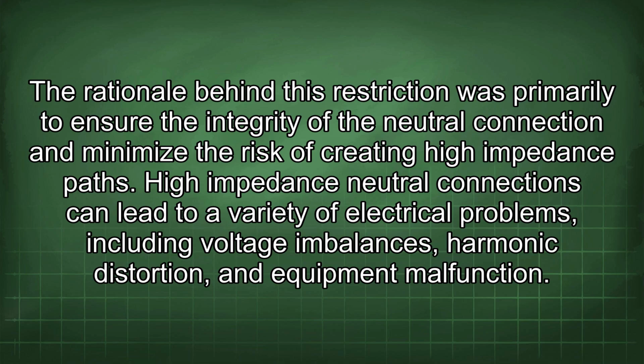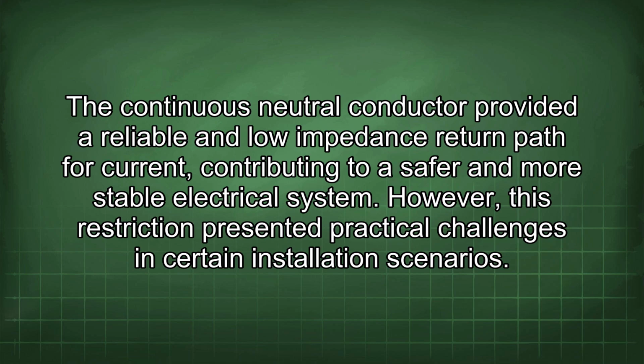High impedance neutral connections can lead to a variety of electrical problems, including voltage imbalances, harmonic distortion, and equipment malfunction. The continuous neutral conductor provided a reliable and low impedance return path for current, contributing to a safer and more stable electrical system. However, this restriction presented practical challenges in certain installation scenarios.